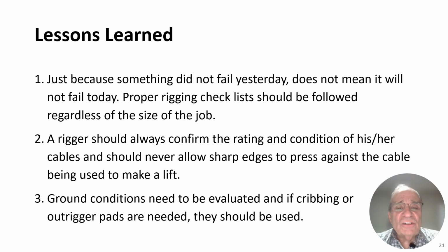Well, that purging procedure had been used for years. It was a normal purging procedure. It was a pressure purging process. It was not fully evaluated properly, and although it hadn't failed in prior times, it failed. There was a source of ignition, and it ended up causing this damage and gave the industry a black eye as well. So just because it didn't fail yesterday does not mean it will not fail today. It is a caution that I always give operators and maintenance personnel. If there's any risk associated with the job, it should be evaluated. And even if it's been done 100 times before, how many explosions does it take to hurt you? Only one.